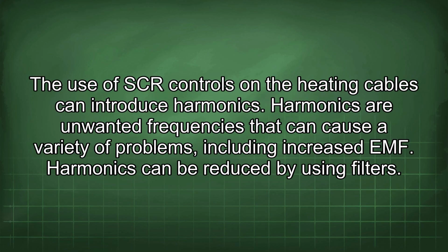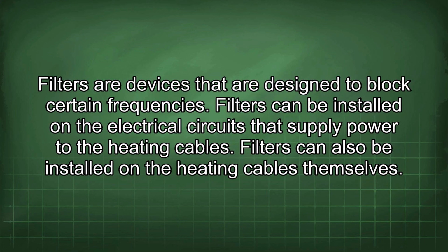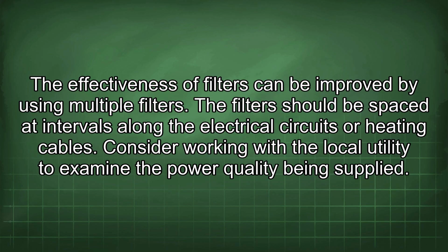The use of SCR controls on the heating cables can introduce harmonics. Harmonics are unwanted frequencies that can cause a variety of problems, including increased EMF. Harmonics can be reduced by using filters. Filters are devices that are designed to block certain frequencies. Filters can be installed on the electrical circuits that supply power to the heating cables. Filters can also be installed on the heating cables themselves. The effectiveness of filters can be improved by using multiple filters. The filters should be spaced at intervals along the electrical circuits or heating cables. Consider working with the local utility to examine the power quality being supplied.